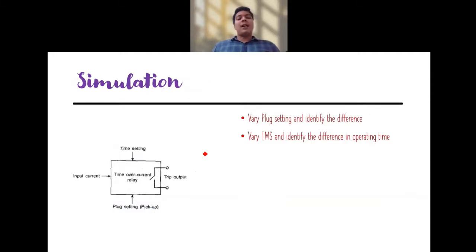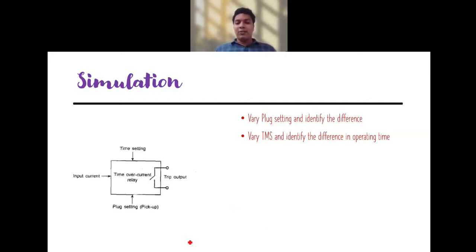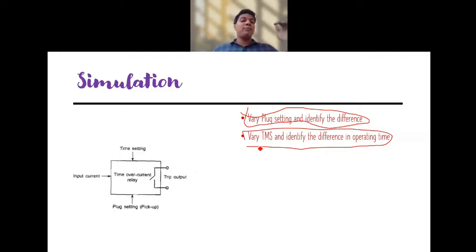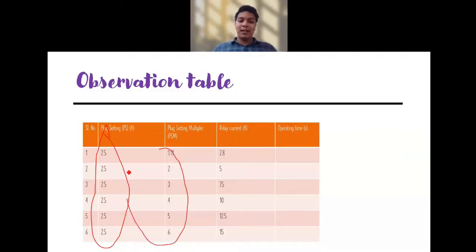In the simulation, we will vary the plug setting multiplier and see the difference, and also vary the TMS to identify the difference in operating time. Our concentration will mainly be on TMS variation rather than plug setting. Plug setting of 3 ampere means the relay operates above 3 ampere current; at 5 ampere it operates above 5 ampere. For IDMT characteristics, in the observation we will stick with one plug setting of 2.5 ampere due to the limitation in the virtual lab platform.